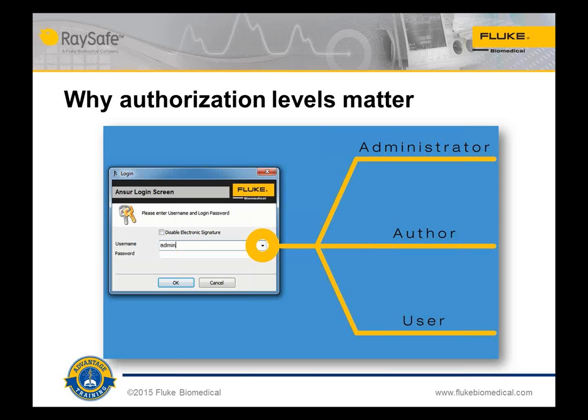Why does authorization level matter? Quality assurance best practice tells us that workflows need to be created and controlled so they comply with inspection and testing requirements, and so they produce results that are statistically sound. The workflow sequence is always the same and not allowed to vary from one operator to the next or one day to the next. Variables in configuration of the device under test, like variation in models, modules, or accessories, need a way to report what's available on the day of testing, no matter what was expected. All of this needs to be pre-planned and handled in the workflow.